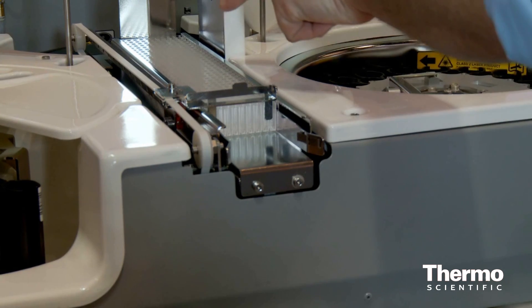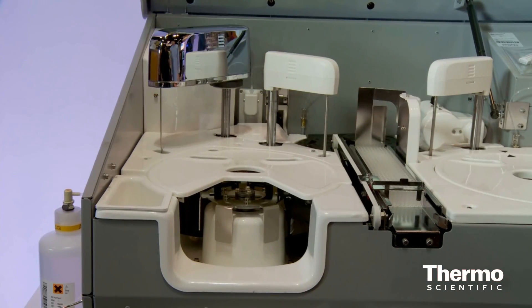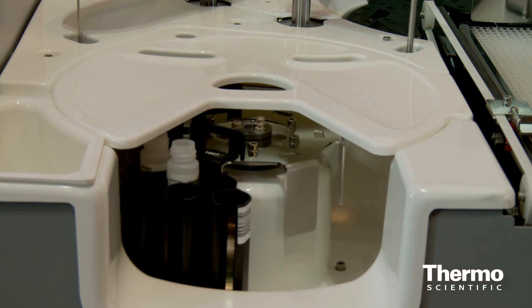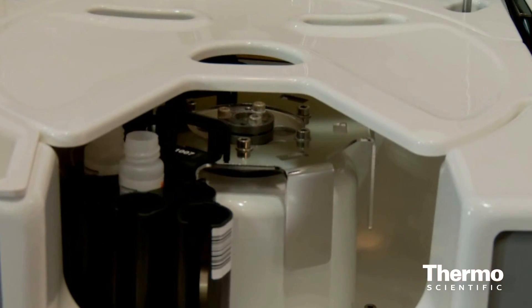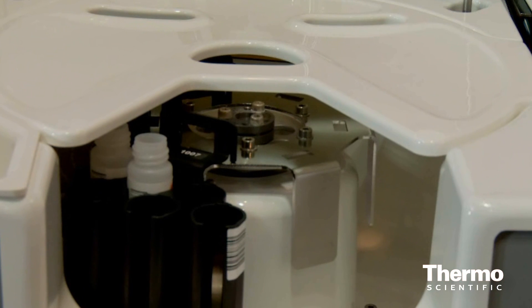We can do other tests for beers — for example, sugars and organic acids. If you had 13 assays plus the bitterness test, the instrument has a throughput of up to 100 tests per hour. There are dispensers that move the sample and the reagent into cuvettes, and each cuvette is a discrete test where one test is done and it's thrown out, and a new cuvette can be brought in.